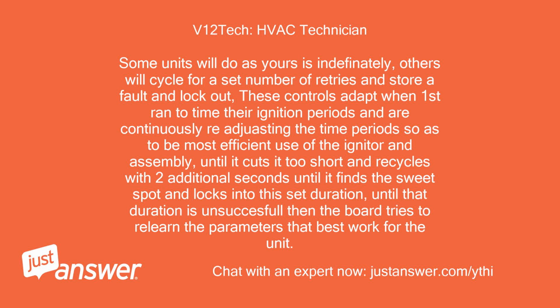Some units will do as yours is indefinitely, others will cycle for a set number of retries and store a fault and lockout. These controls adapt when first run to time their ignition periods and are continuously readjusting the time periods so as to be the most efficient use of the igniter and assembly, until it cuts it too short and recycles with 2 additional seconds until it finds the sweet spot and locks into this set duration. Until that duration is unsuccessful, then the board tries to relearn the parameters that best work for the unit.